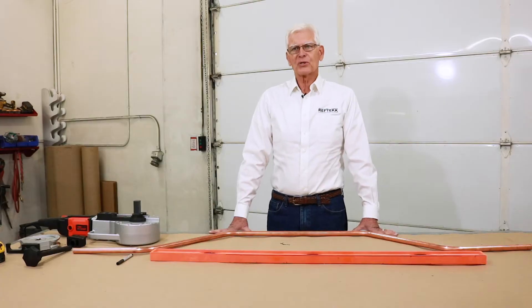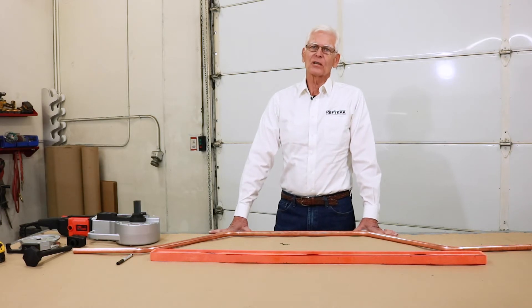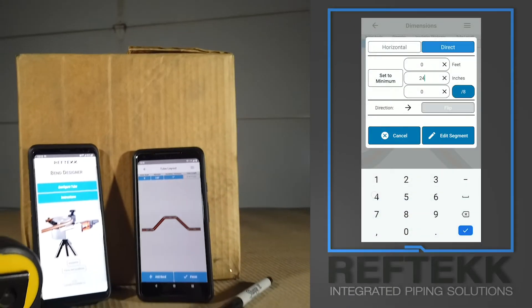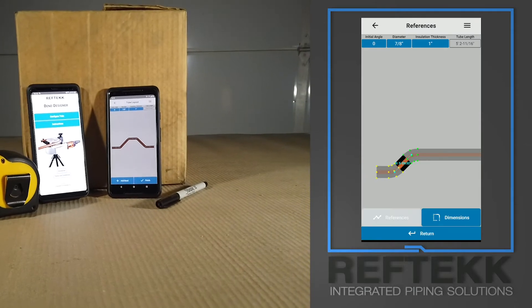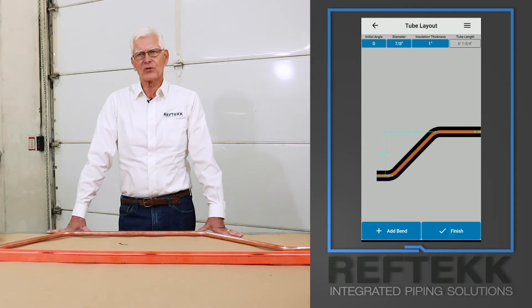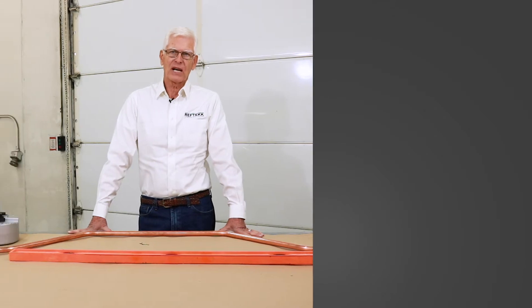Bending copper tube and making it go where you want it to is a learned skill. It also requires a little bit of math for precision bends. The Reftekk bending app for Android and iOS is very helpful for precisely bending tubing. Another training video will go into depth on how to use the app, but in this demonstration we will just be using the app's output. For this demonstration we're going to make a four-point saddle bend with 45 degree bends using 7/8 OD half hard copper.